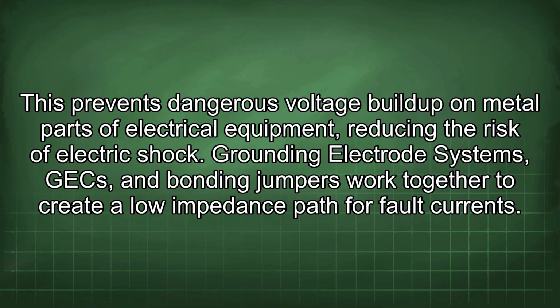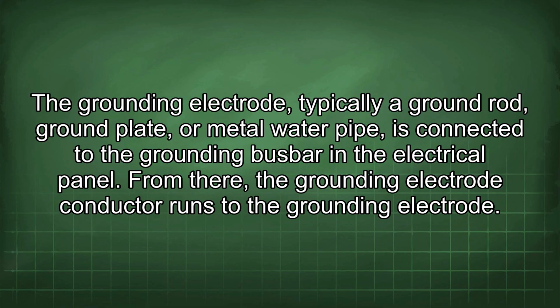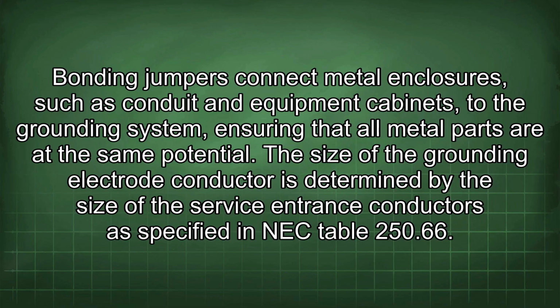Grounding electrode systems, GECs, and bonding jumpers work together to create a low-impedance path for fault currents. The grounding electrode, typically a ground rod, ground plate, or metal water pipe, is connected to the grounding busbar in the electrical panel. From there, the grounding electrode conductor runs to the grounding electrode. Bonding jumpers connect metal enclosures, such as conduit and equipment cabinets, to the grounding system, ensuring that all metal parts are at the same potential.